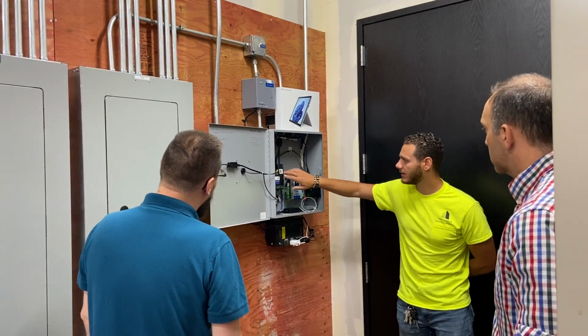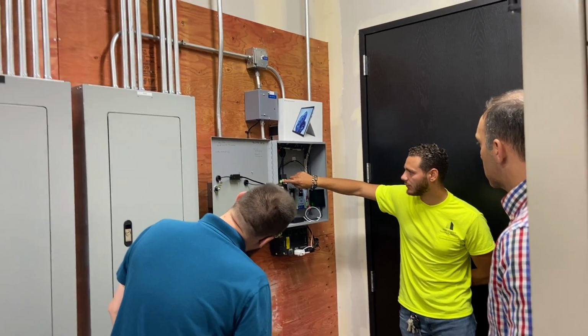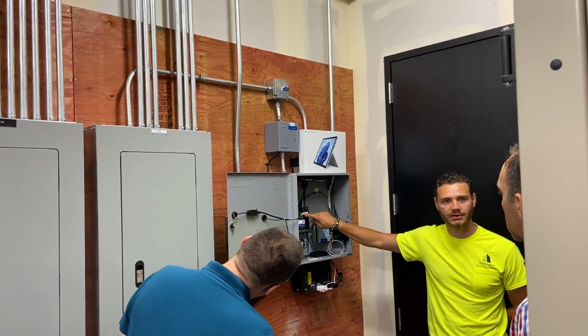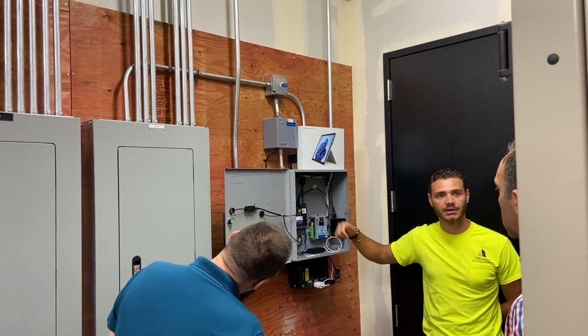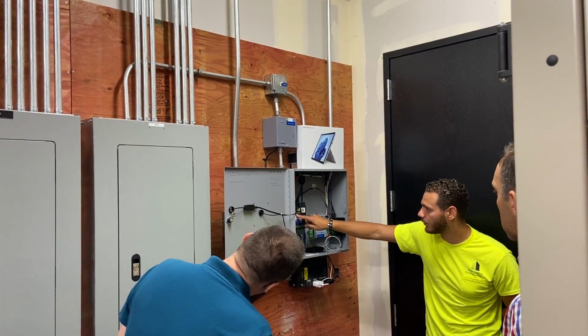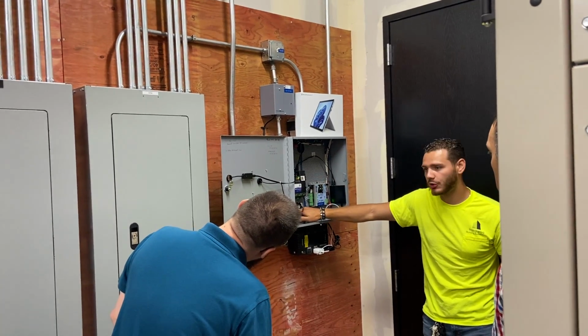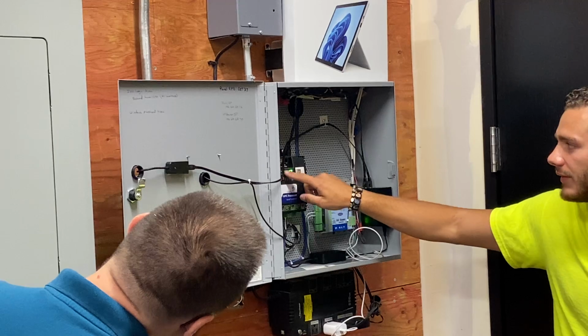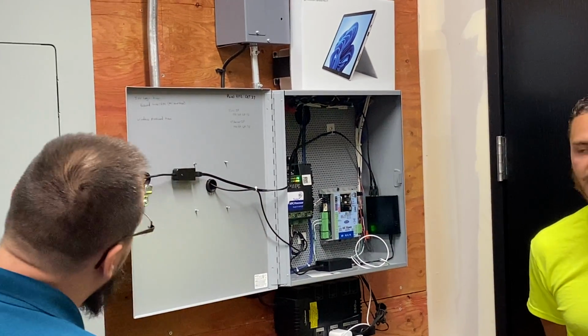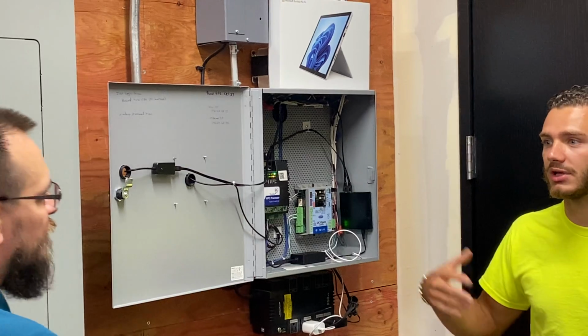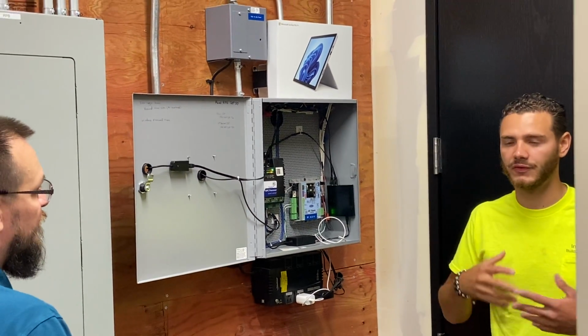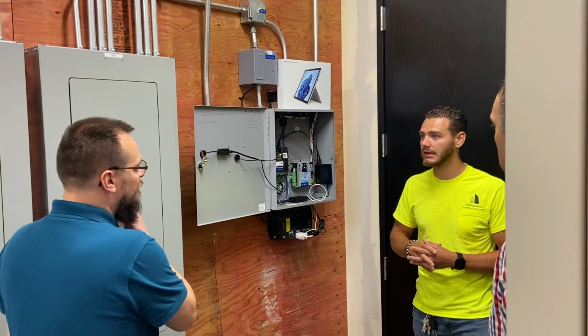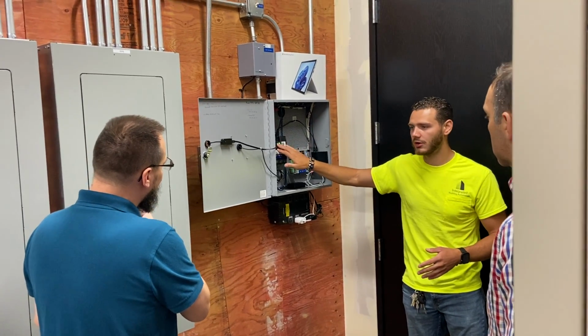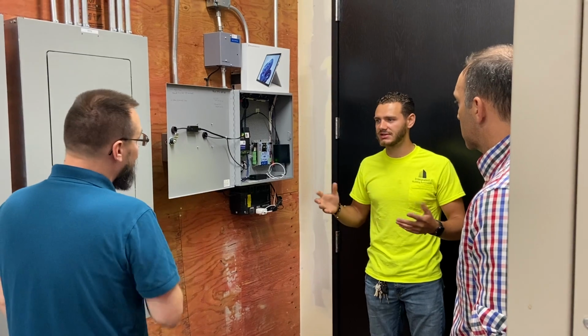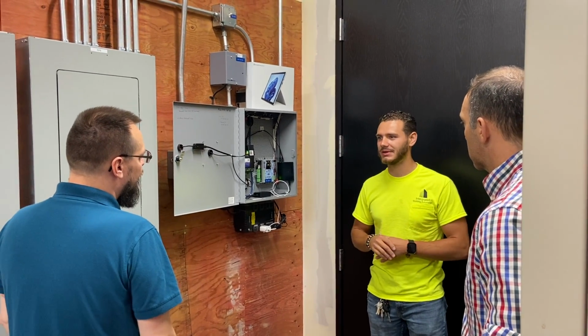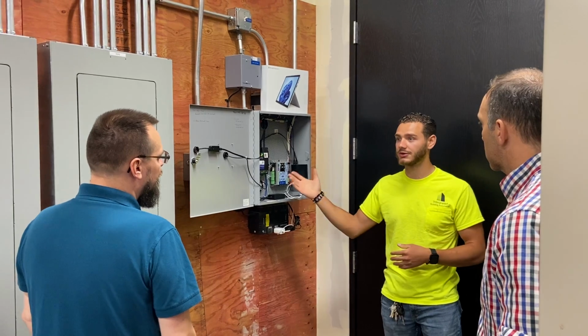But if we're checking, we have our system and network light here, blinking solid green, which is good. If it's blinking orange, we're not communicating. Then we have port 1 and port 2, our network ports that communicate with our devices, and we see those systematically flashing back and forth, letting us know we're sending and receiving signals and everything is active. So for troubleshooting, if devices aren't communicating, we can open this and reference these lights. They do have a sequence, not something we keep in the tablet, but if you reach out to us, we can try to troubleshoot that way.